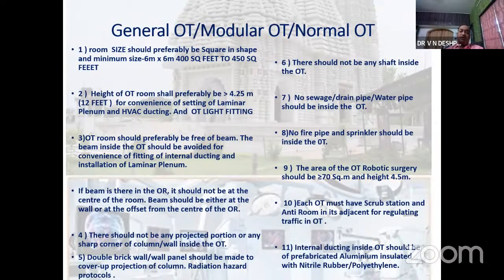General considerations: what should be the room size? The room size of the main operation theater should be 400 to 450 square feet. The height of the operation theater should be at least 12 feet below the false ceiling to have good plenum, good HVAC ducting, and OT light fittings. The OT room should preferably be free of beams, free of columns. The beam in the OT, if at all, should be avoided in the center and it can be taken a little offside. If the beam is there, it should be out of the center. There should not be any projection or any shaft or any column.